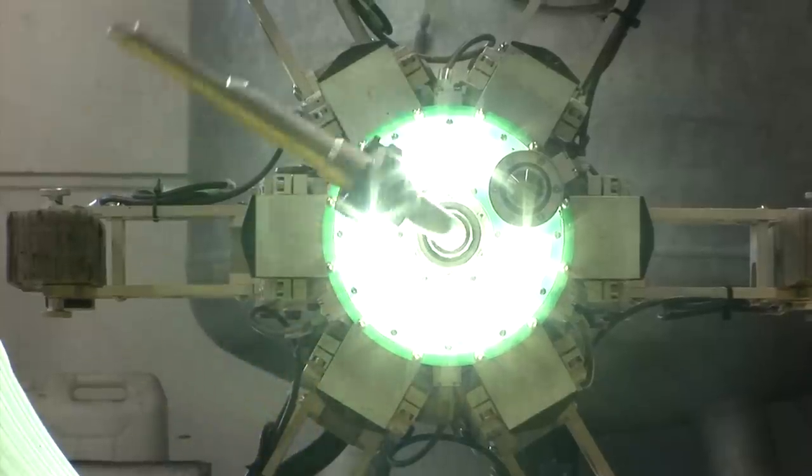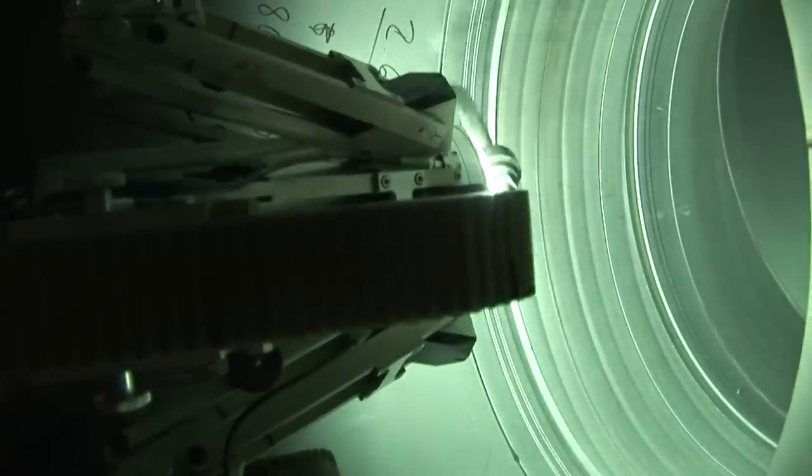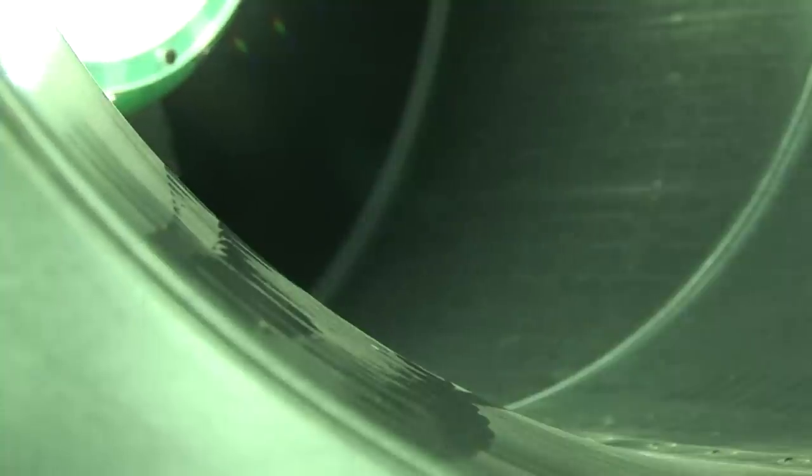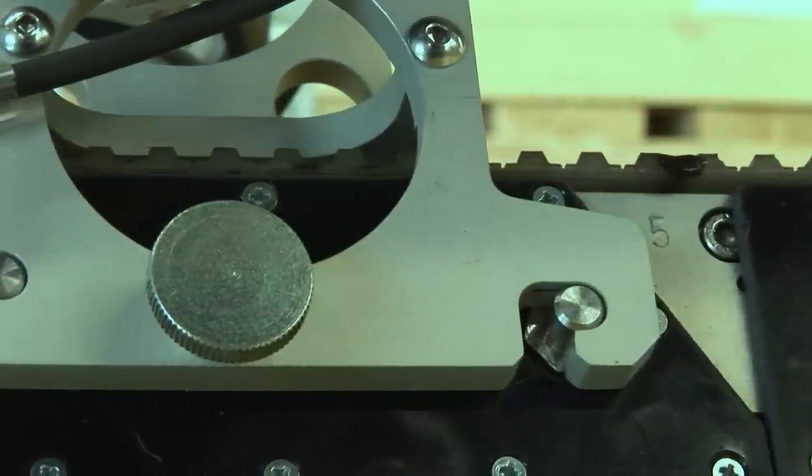The rotation velocity of the nozzle and the robot's movement speed can be adjusted according to the extent of contamination. The cleaning medium is sprayed from the nozzle at minus 78 degrees Celsius. It quickly super cools the surface and causes thermal shock. As a result, the contamination is released due to the differences in the tension between the contamination and the underlying surface.